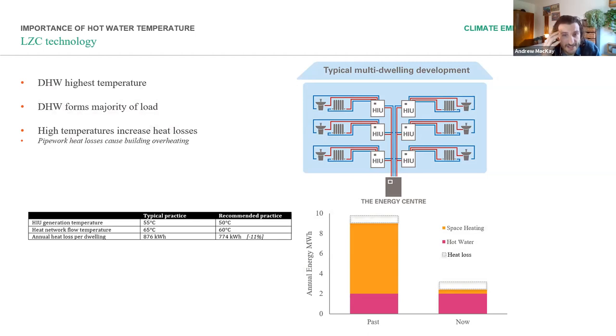We can use space heating down at 35 degrees if we wanted to, and we'd have some big emitters, but that would be okay. We could get that to work. But actually, we know that we need hot water to be a certain temperature, whether that's for function or for safety. So that brings the temperature of the network right up, which drives the heat losses and drives the technology that we use.